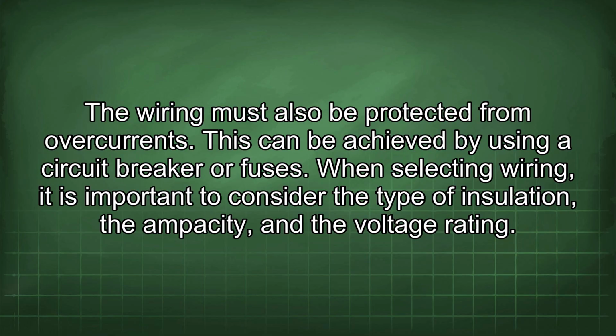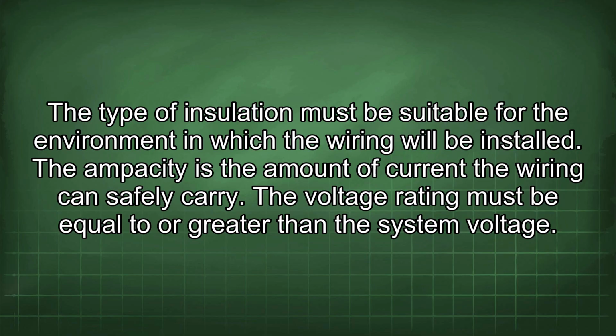When selecting wiring, it is important to consider the type of insulation, the ampacity, and the voltage rating. The type of insulation must be suitable for the environment in which the wiring will be installed. The ampacity is the amount of current the wiring can safely carry. The voltage rating must be equal to or greater than the system voltage.